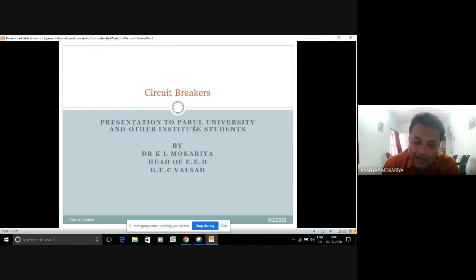Why I thought to give this presentation: while I was working with breakers, I saw that students studying in diploma, BE or ME only understand that a breaker is used for transmission lines. No, we have a different role in industry. Suppose at Reliance Industries Limited we have a motor rated up to 90 kilowatt, operated by means of a starter. Let us clear a doubt here: in books it is written that a direct online starter can be used for a motor up to 5 HP only, but those industries which have a strengthened source, or devices that can compensate a voltage dip, use a DOL starter and a star-delta starter up to 90 kilowatt.